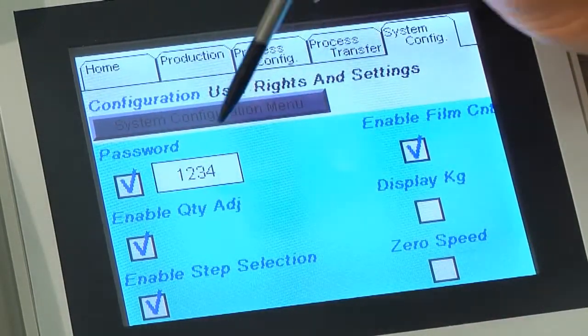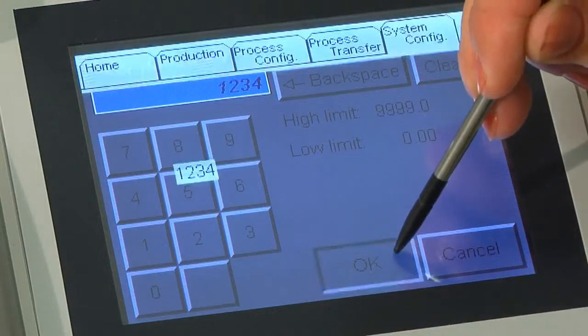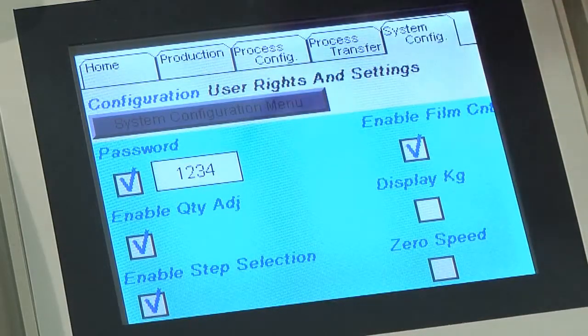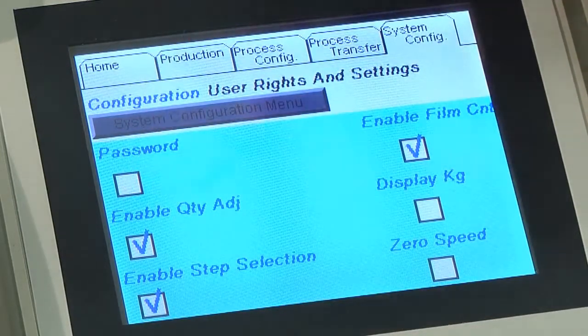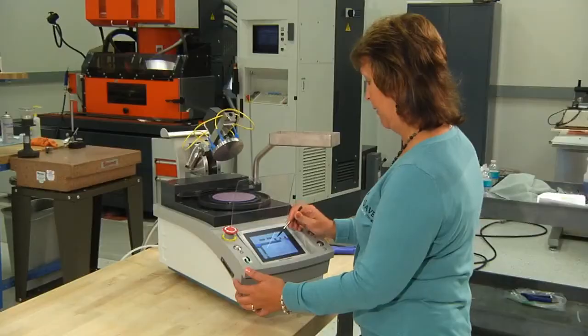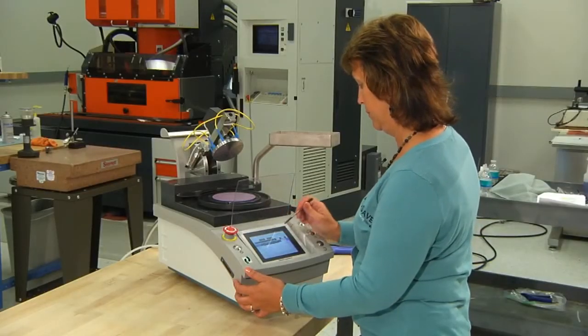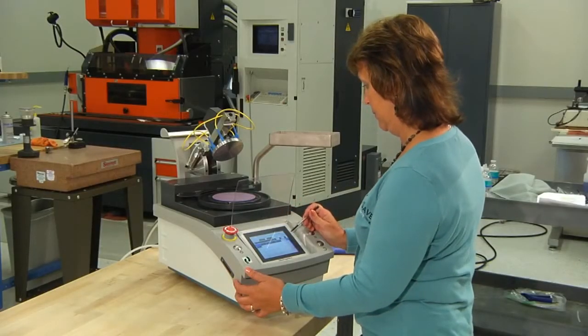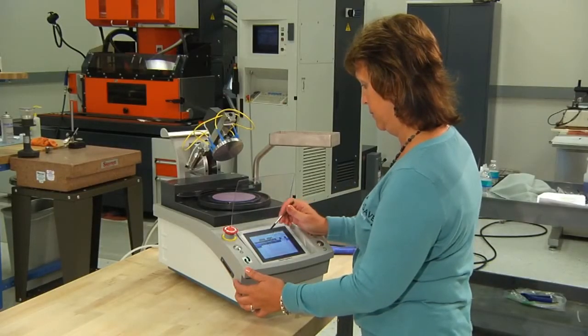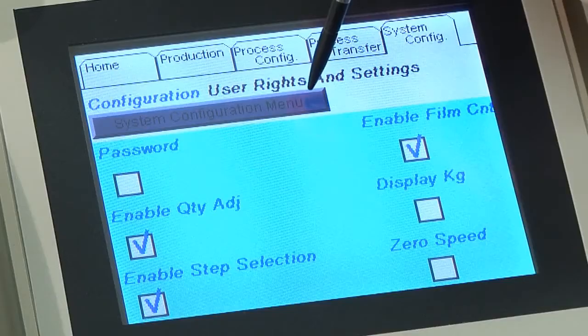Also on this screen is the password protect option. Here you can lock the operator out of the process configuration so the process cannot be altered. This will allow the operator access only to the home and production screens.